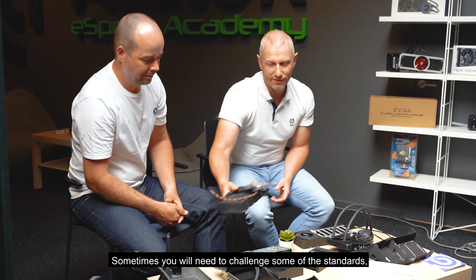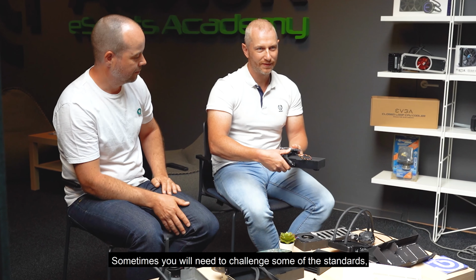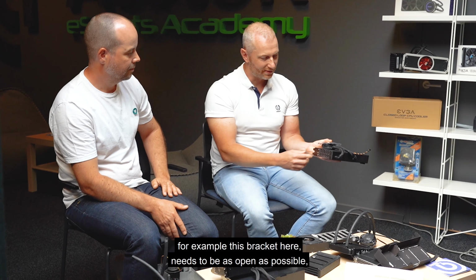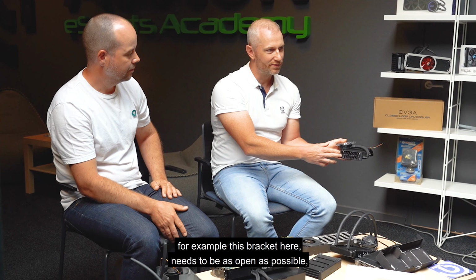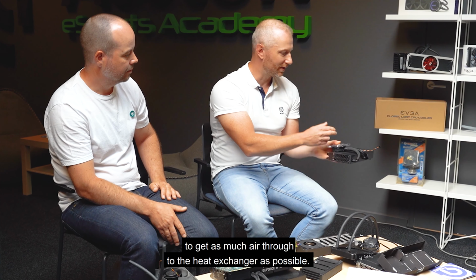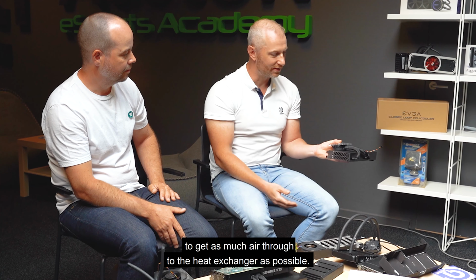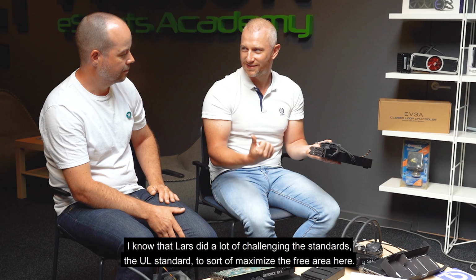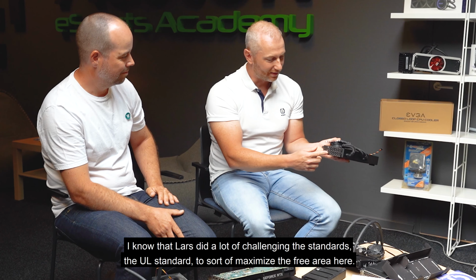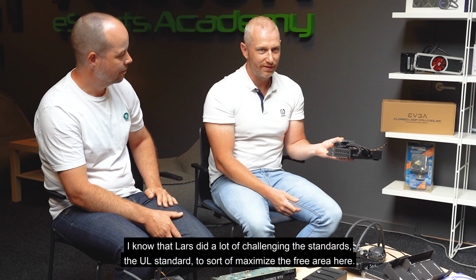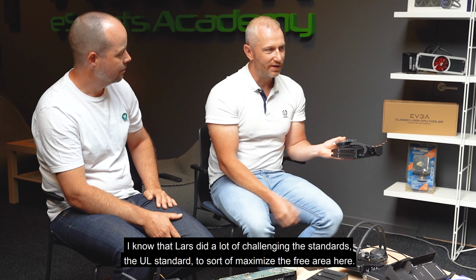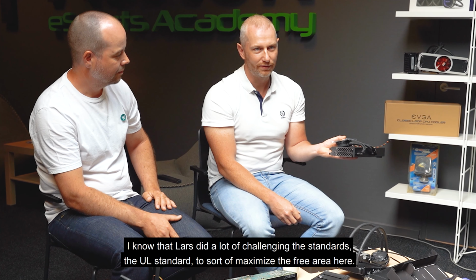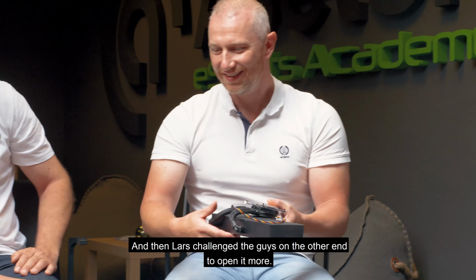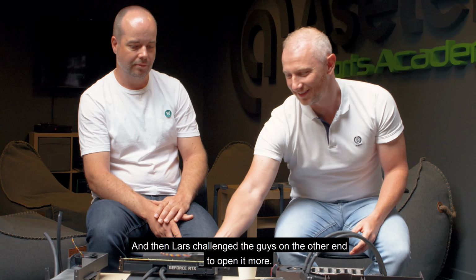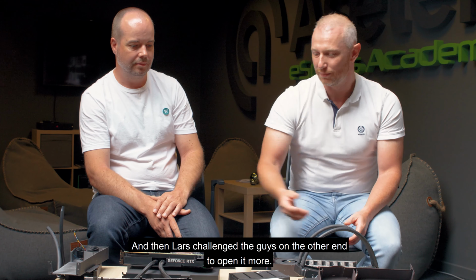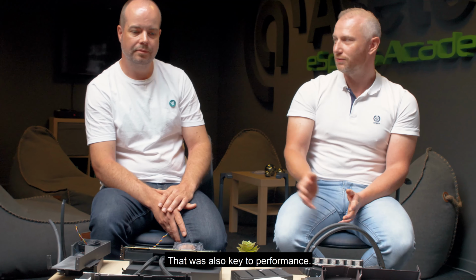Sometimes you would need to challenge some of the standards. For example, this bracket here needs to be as open as possible to get as much air through the heat exchanger as possible. So I know that Lars did a lot of challenging the standard, the UL standard, to maximize the free area here. And then Lars challenged the guys on the other end to open it more. That was also key to performance.